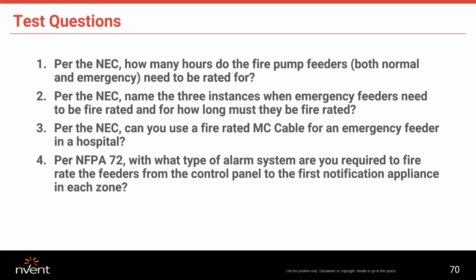And this cable is quite strong mechanically. I should add, it can withstand 120,000 PSI. You can crush this cable to half its diameter and it'll still remain electrically functional. And that's because the magnesium oxide is denser than the copper. So, as I said, you can crush this cable and the copper still won't come in contact with the sheath because the density of the magnesium oxide is so great.